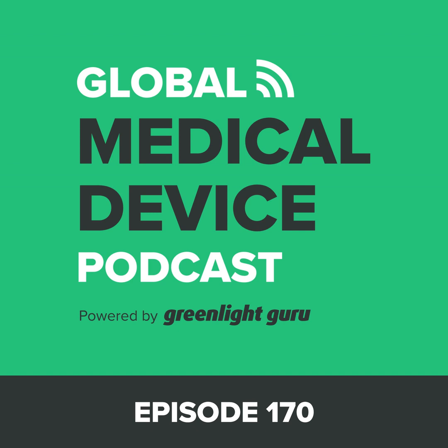Certainly. So we have a lot of clients come to us that are sometimes early stage medical device companies or software companies that want to expand into a medical claim. And they have the question, okay, what do we need to have for that first step with the FDA? What do we need to have for that first conversation and see where we sit in terms of regulatory pathway, get that initial feedback from FDA in terms of what they're going to expect us to do for our device? And typically, that first interaction for most medical devices would be a pre-submission meeting. I'm sure most of your listeners are familiar with that.